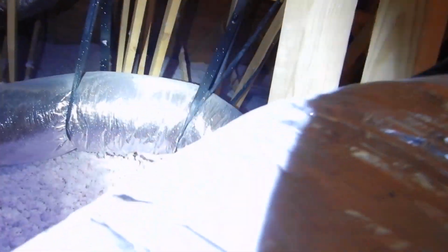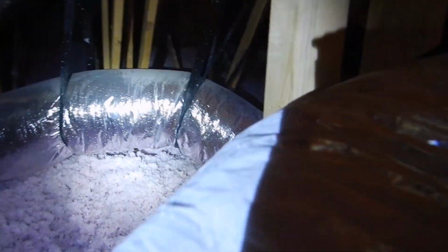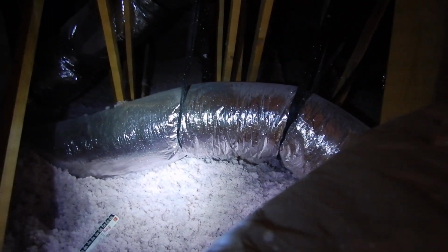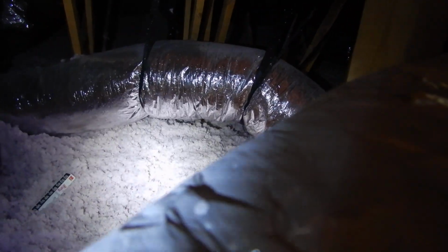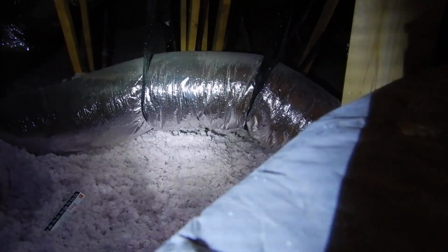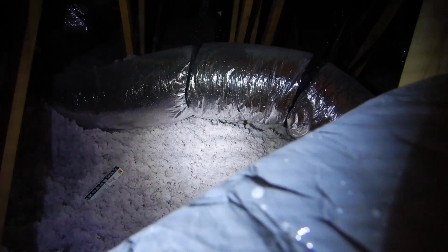People gotta adapt. And then see these straps that come down here? They should have cardboard underneath the straps so the straps don't pinch and bind the duct, and metal would be better, but at least cardboard underneath these straps, these webs is what that's called. And the webs, you should have cardboard underneath there so they don't cut into and bind your air conditioning duct. Let's see what else we got here. Okay, there's our zones 1 and 2.